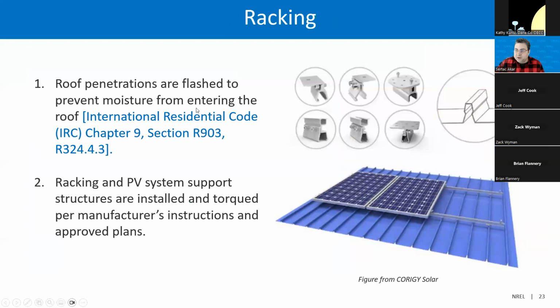And after PV, we continue with the inspection of the racking. The inspector should verify that the roof penetrations are flashed to prevent moisture from entering the roof, and that racking and PV system support structures are installed and torqued per manufacturer's instructions and approved plan. You can see a couple of examples of connectors and racking applications in this figure, and you can find more information about these in the International Residential Code, Chapter 9, Section R903.